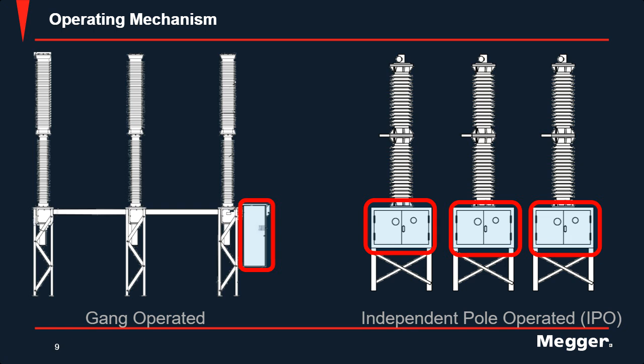When it comes to IPOs, independent pole operated, there is one mechanism per individual phase. It's generally above 245 kV. However, for voltages below 245, you could use these in special applications such as synchronous switching or higher amperage ratings. They can also be used to trip and reclose on only one phase if there is a single phase fault.